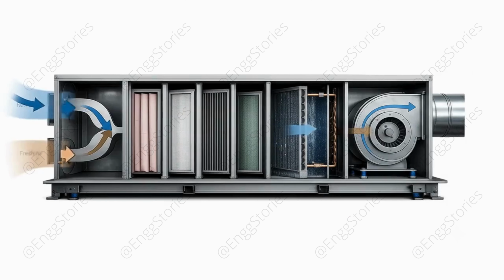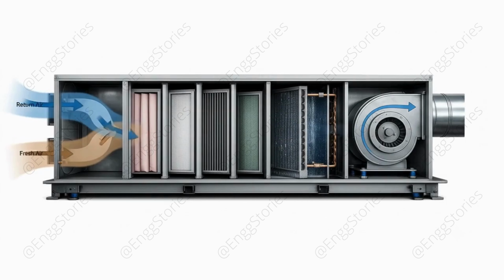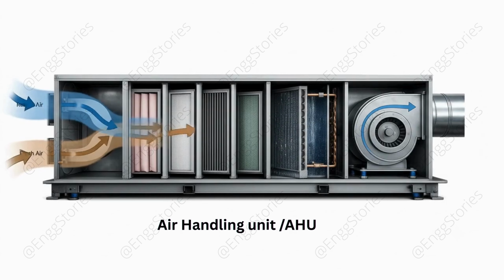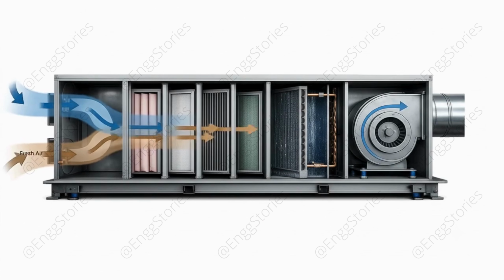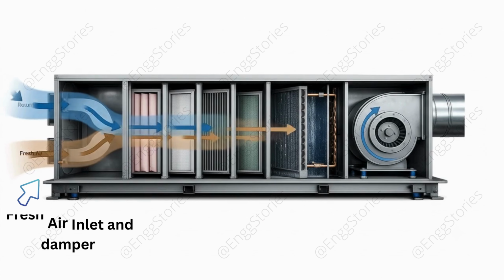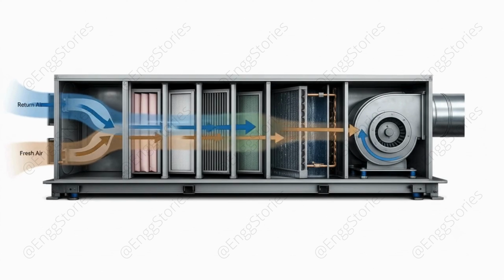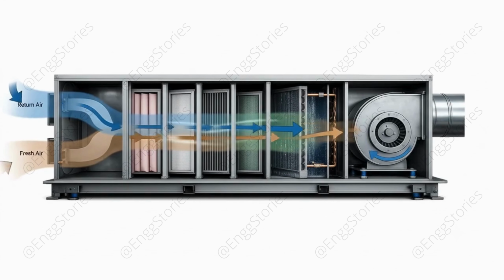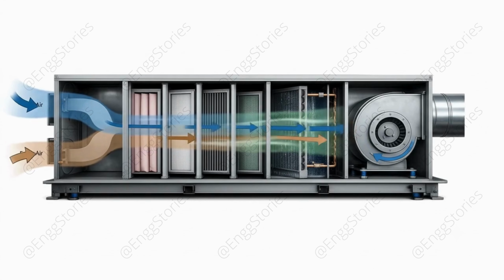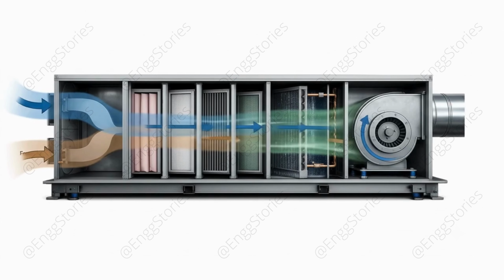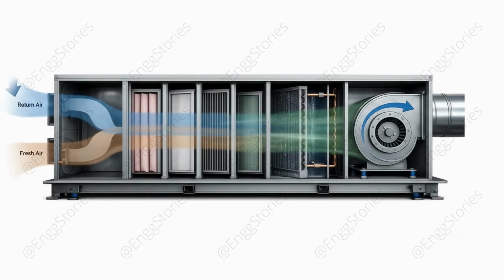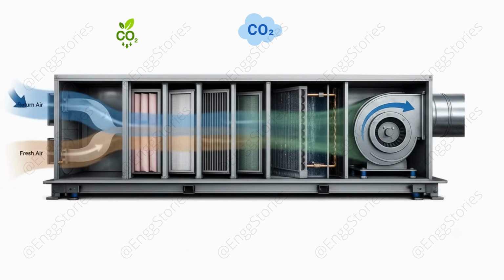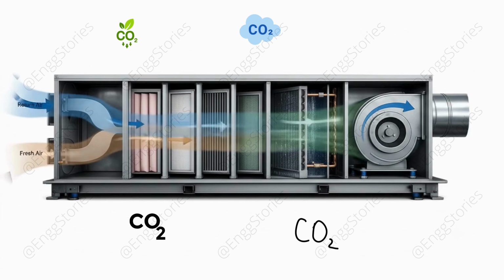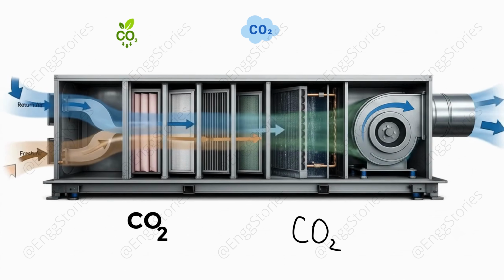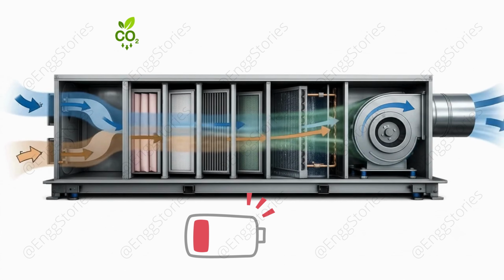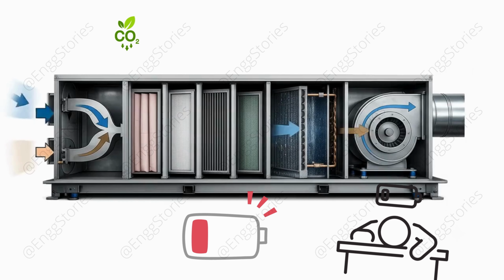Now, let's see how air enters the AHU. An air handling unit, or AHU, usually has two air inlets. One inlet brings in fresh air from outside the building, and the other brings in return air from inside the building. You might wonder, why don't we just recirculate all the return air? The reason is indoor air quality. As people breathe, they release carbon dioxide, CO2. If we keep recirculating the same air without adding fresh air, the CO2 level inside the building keeps increasing. High CO2 levels can make people feel tired, sleepy, and uncomfortable.